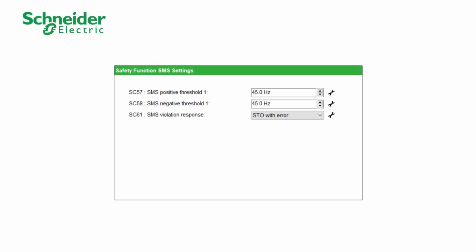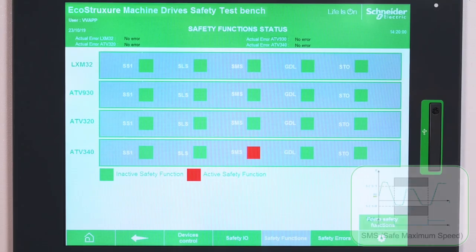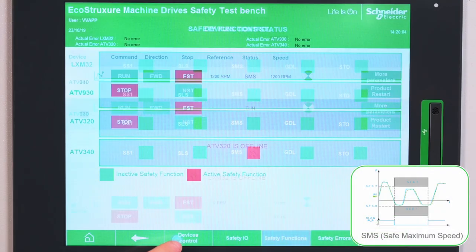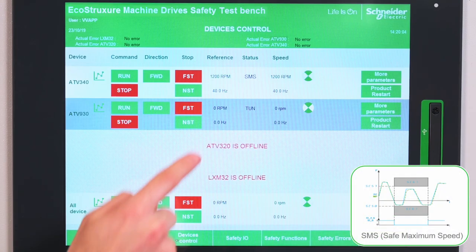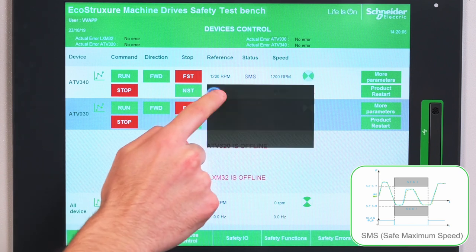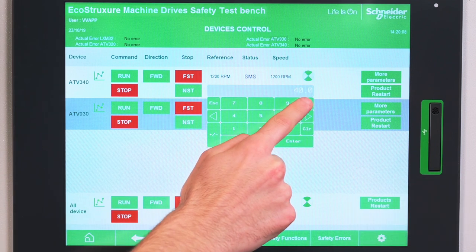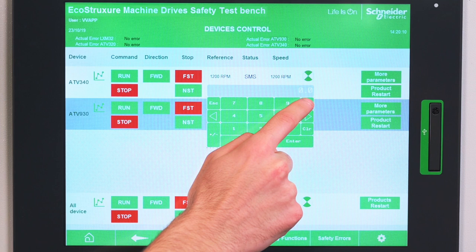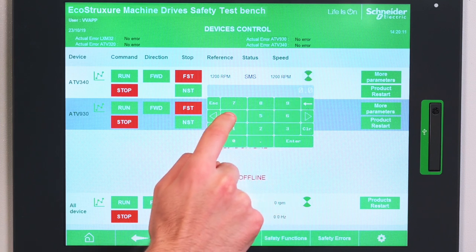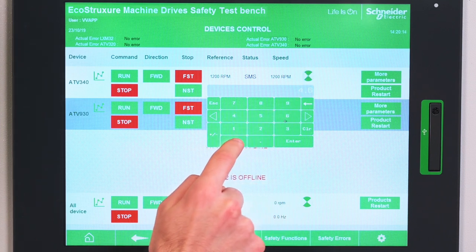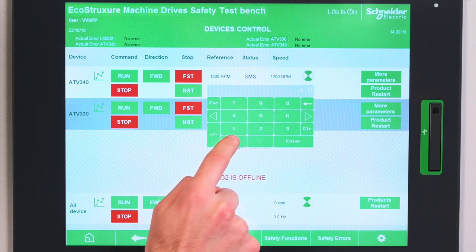We configured SMS using SoMove. We can see that SMS is activated on the HMI. When the motor is running below the SMS limit, the motor keeps its current speed. When we increase speed over the maximum speed, the motor trips in STO and stops in freewheel.